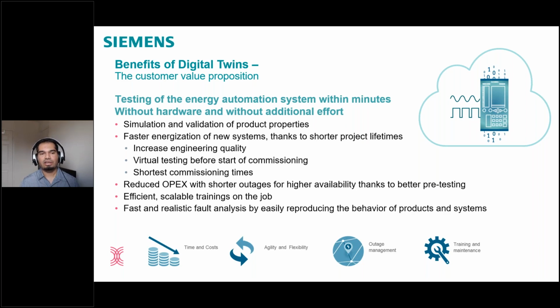And then fast and realistic fault analysis by easily reproducing the behavior of products and systems. So this relay will behave exactly as a physical protection relay — it will run the same algorithms as a physical protection relay. So if you want to reproduce fault behavior, you will reproduce it for sure by using the ComTrade file which you have got from the site.